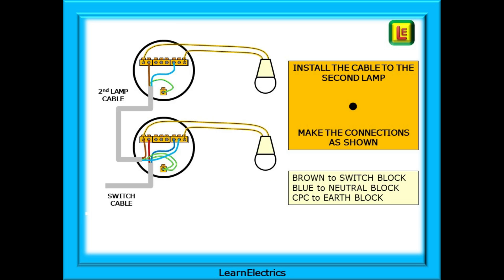Now we can install the cable from ceiling rose number one to ceiling rose number two, the second lamp. The new connections are the same at both ceiling roses. The brown into the two-hole switch block on both ceiling roses. Then on both we connect the blue into the outside block of three holes, the neutral block, and not forgetting the CPC into the earth terminal at both ceiling roses. And that is the job done.